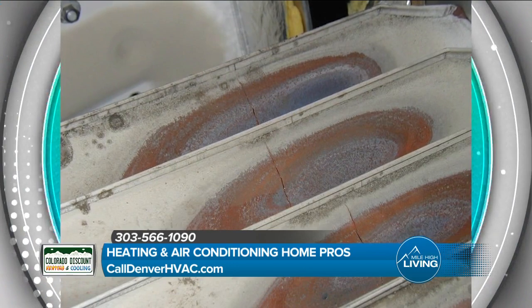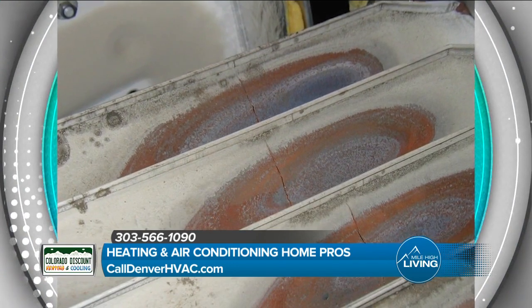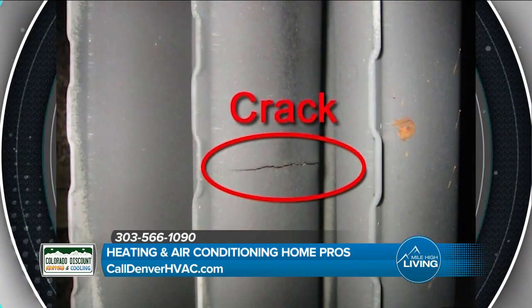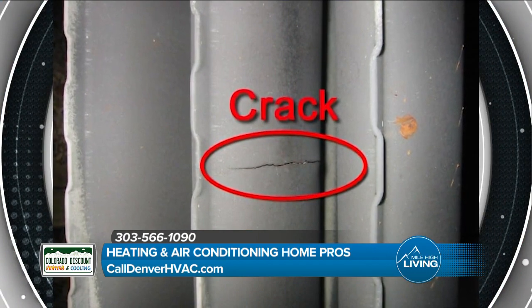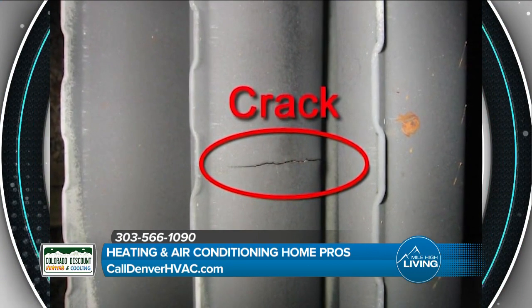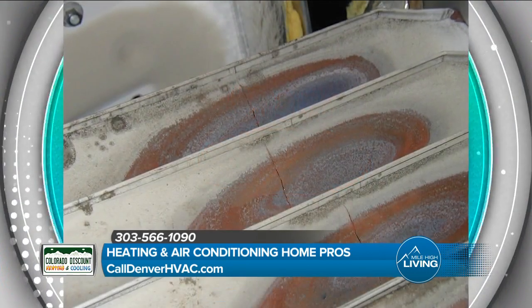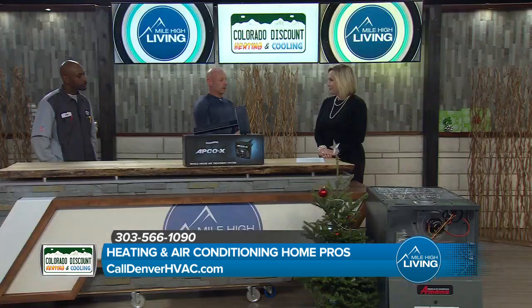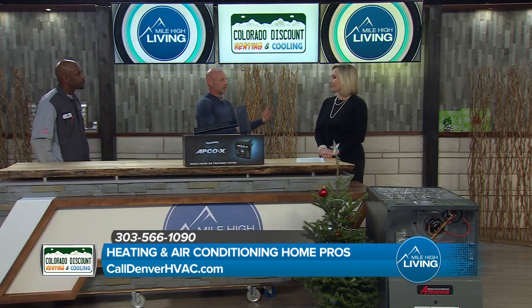Last thing you can do is take a temperature reading at your supply vents where the air comes out, and another where your air is going back into the system at the filter. You should have a 25 to 50 degree split there to know the air going in is being heated properly to get into the space and keep you comfortable.